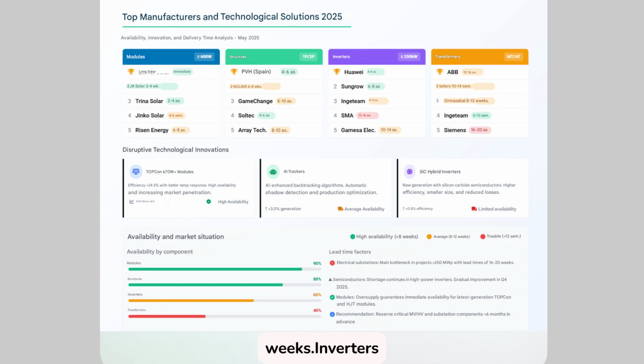Inverters, 250 kW: Huawei and SunGrow have rapid availability, 4-8 weeks. Ingeteam and SMA exceed 8 and 12 weeks, respectively. Gamesa Electric delivers in 10-14 weeks. MV/HV transformers. This is where the problems begin. ABB and Siemens are in the 12-20 week range. This is the main current bottleneck for projects over 250 MWP.